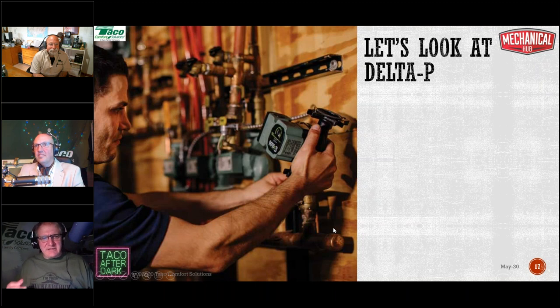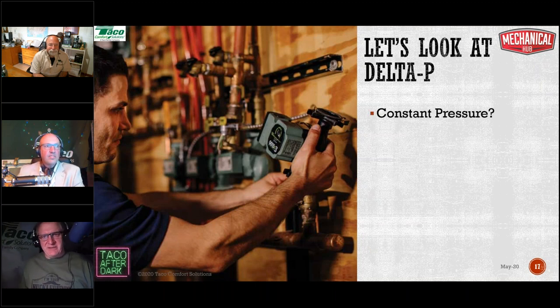All righty. Now let's take a look at delta P and how delta P can help things work. A lot of people look at delta P as a constant pressure, where the circulator tries to adjust the pressure to different loop lengths, a pressure regulated circulator. That's really an incorrect statement. It's resistance regulated. It changes its speed and functioning based on the resistance the impeller is encountering. In a constant pressure mode, which is the mode you want for zone valve applications, it's trying to maintain a fixed head pressure differential within the system.